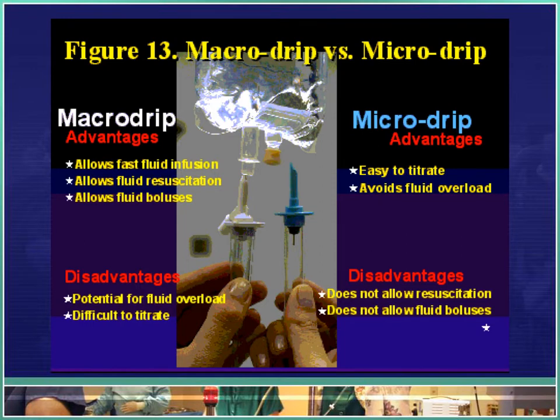This slide illustrates the differences between macrodrip and microdrip infusion sets and indicates the advantages and disadvantages of each. For the macrodrip, the advantages are it allows fast fluid infusion, allows fluid resuscitation, and allows fluid boluses. Disadvantages are potential for fluid overload, and it's difficult to titrate. The microdrip advantages are easy to titrate and avoids fluid overload. Disadvantages are it doesn't allow for resuscitation and it does not allow for fluid boluses.